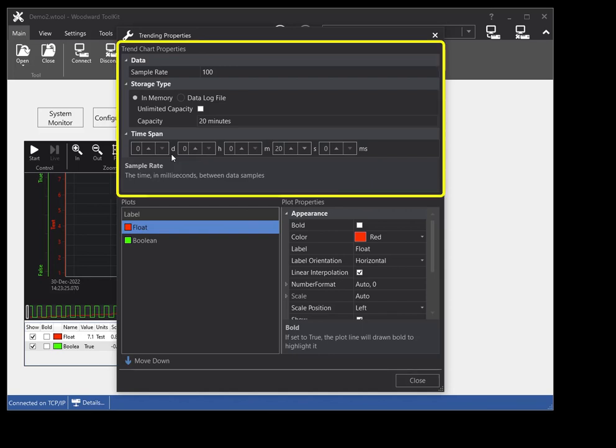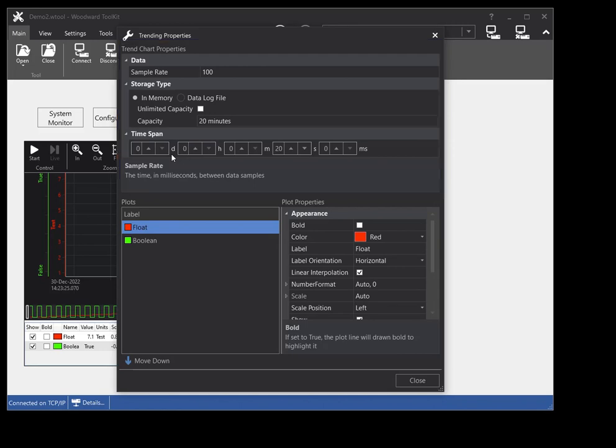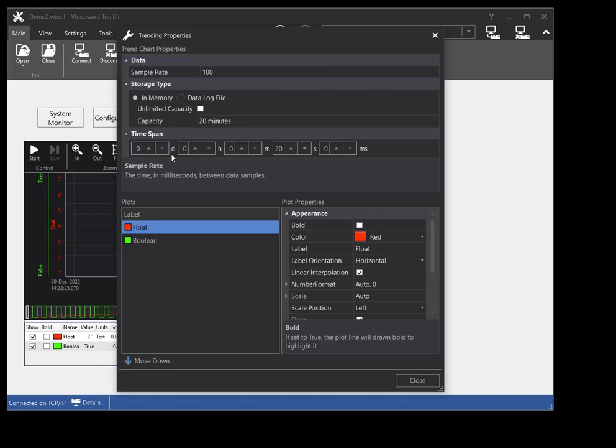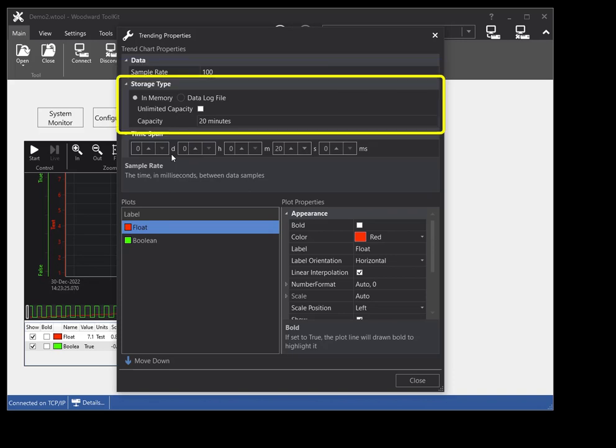The top of the trending properties window contains properties for the trend chart. You can set the sample rate that the plots are updated at. You can set the storage type for the trend chart. There are two storage types: in-memory data log, and to a data log file. The in-memory data log stores the plot data in the memory on the PC. If logging to an in-memory data log, you can set the capacity property to set the data log size.